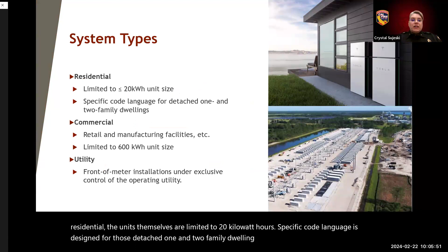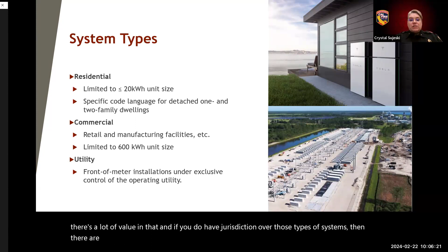So the system types we're going to explore, again at a very high level: residential units are limited to 20 kilowatt hours, with specific code language designed for detached one and two family dwelling spaces. Commercial systems - retail, manufacturing facilities - are limited to a unit size of 600 kilowatt hours. Utilities have front-of-meter installations under the exclusive control of the operating utilities, and there's a lot of value in that. If you have jurisdiction over those types of systems, there are definitely precautions because you're dealing with very high voltages.